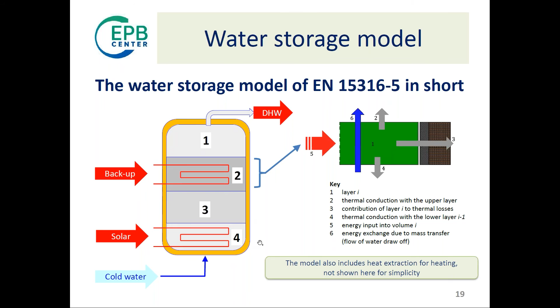What does the storage calculation take into account? During a calculation interval, you have an initial condition - you're first taking out water, so you have cold water at the bottom propagating upward. You might have some heating output, taking heat out, but you take into account that maybe you require 40 degrees, so you're not allowed to take as much energy as you want, only what's available. You might have solar heating in this area, then the backup heater bringing your storage back to 60 degrees, and you arrive at the final solution. All this happens without you noticing - we're just using the available data in the best possible way.